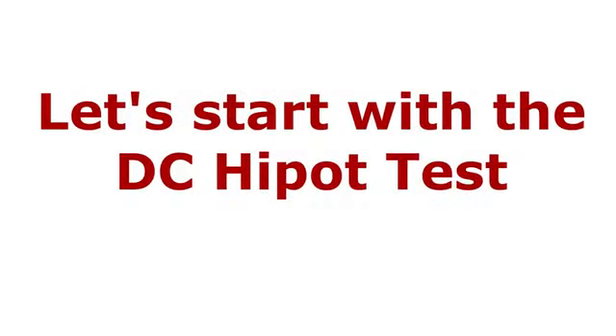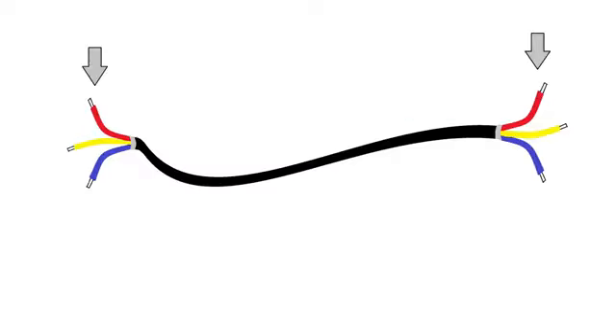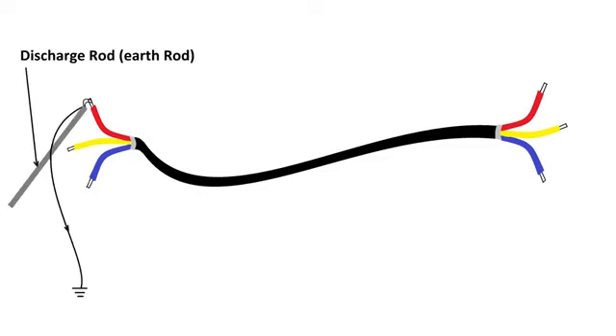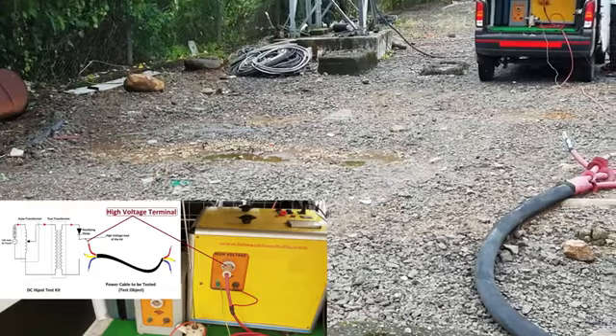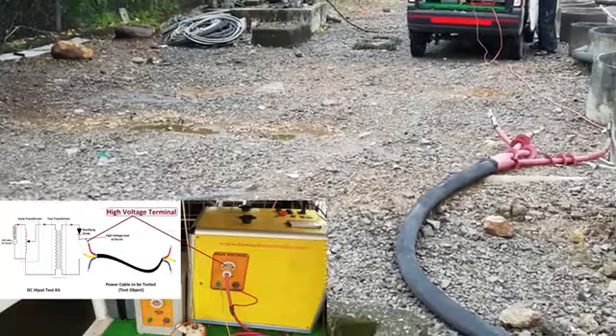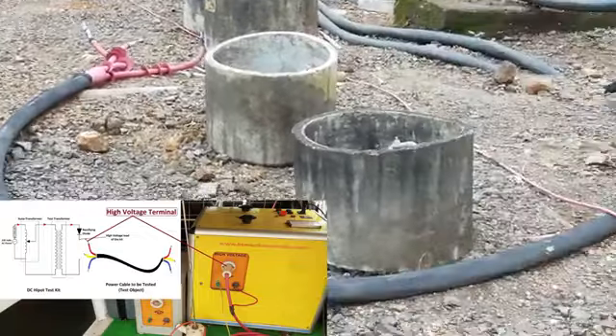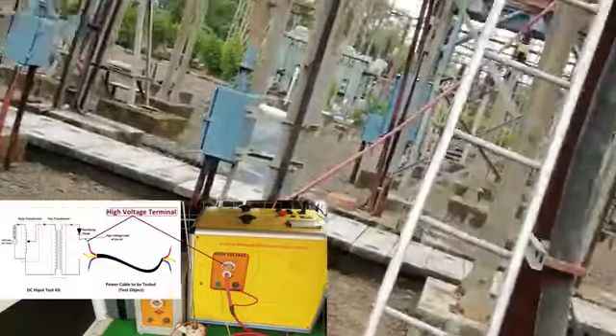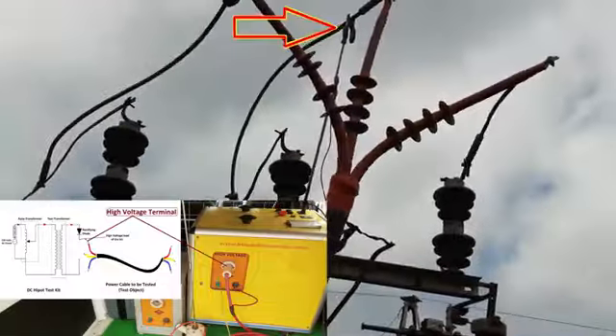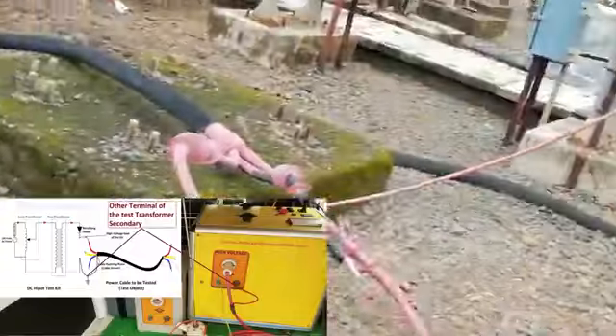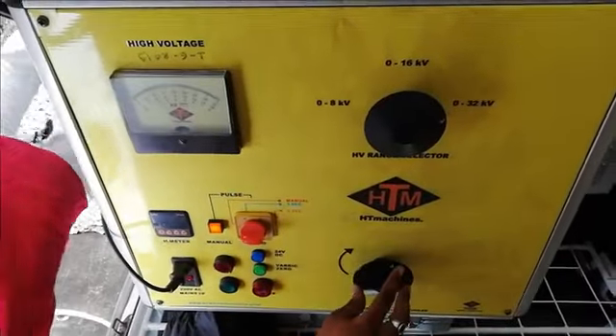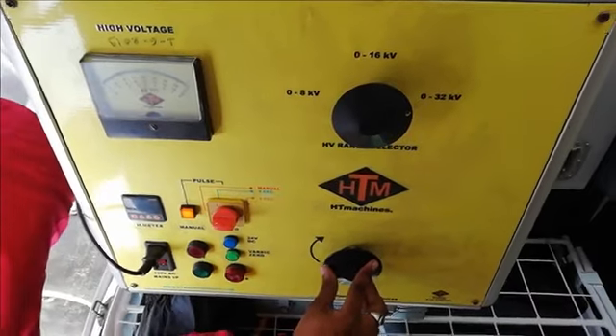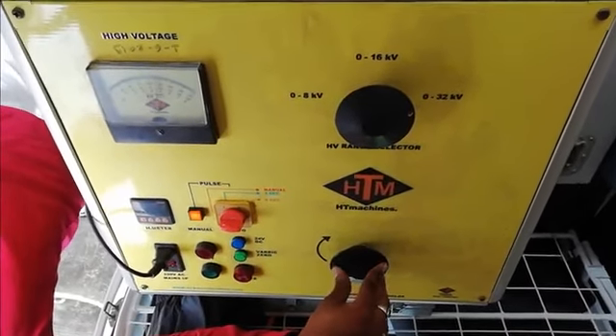Now, let's start with the DC hipot test. First of all, the cable which is to be tested is isolated completely from both ends. And all 3 phases of the cable are discharged using earth rods. This makes the cable free of any possible residual charges and safe to work. Now, this high voltage terminal, which is nothing but the secondary terminal of the test transformer of the kit, is connected to the phase conductor of the cable on which the test is to be done. And this other terminal and cable armor are connected to the ground. To start the test, the on push button is pressed, and using the knob the voltage is raised to the required test level.